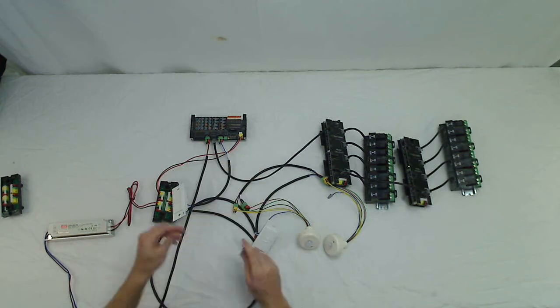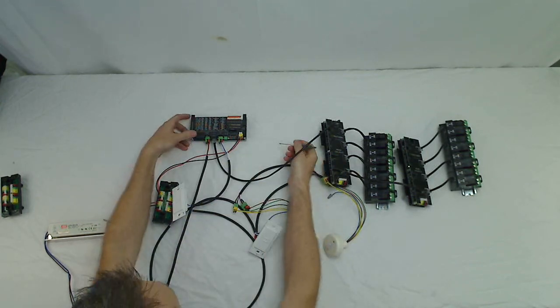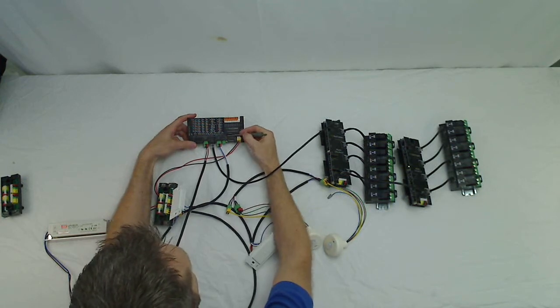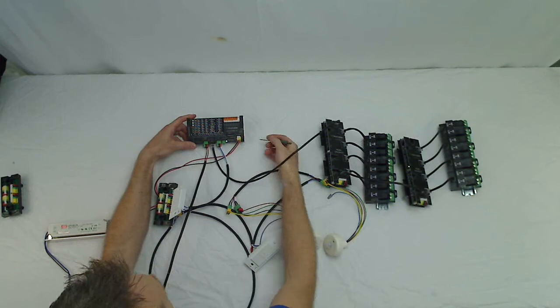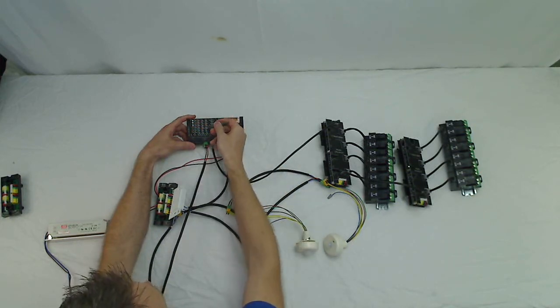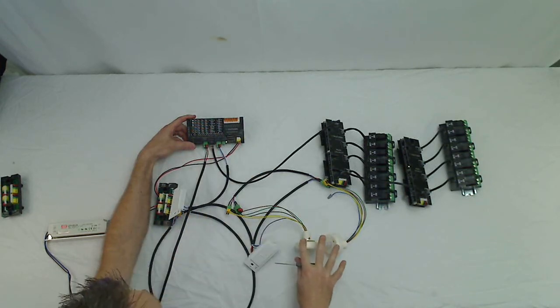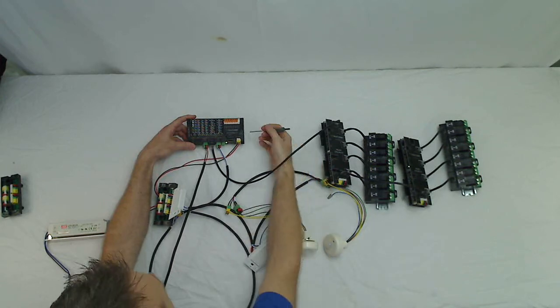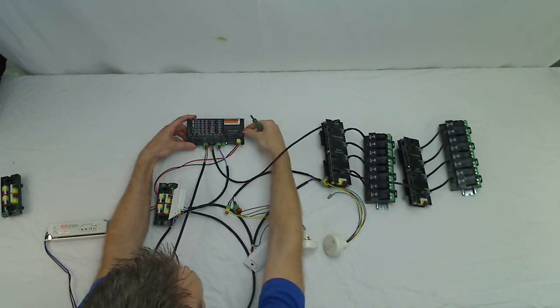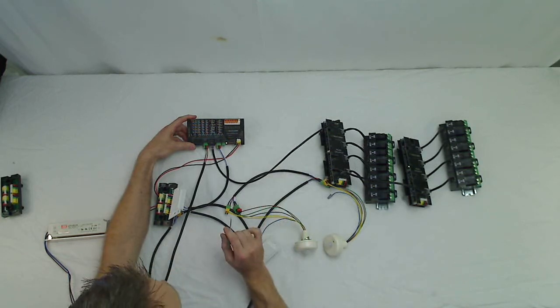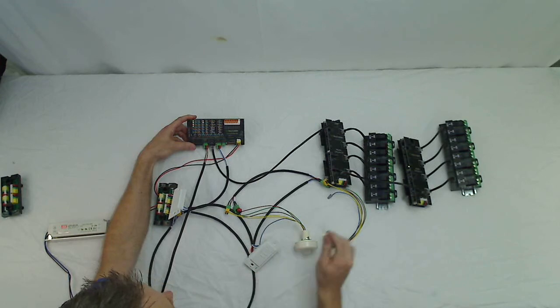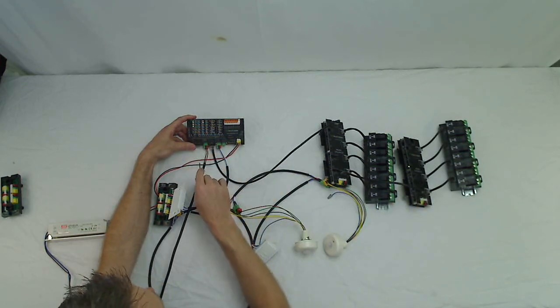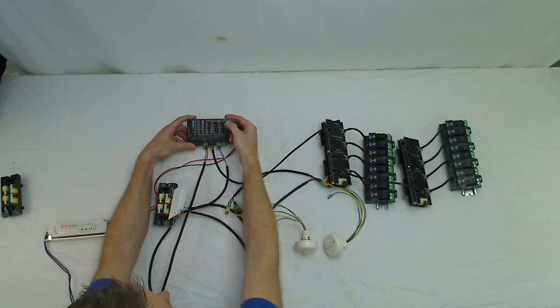So the last thing to do is everything's now wired up for the controller. We'll go to the options dip switches, and we'll turn on dip switch number seven. And we can see here, under our stations, we've already discovered station one, two, three, and four, which is our two wall stations and our two sensors. So now we're going to discover the rest of the stuff on the network. So with dip switch seven on, we press the clear discover button, and it will discover, rediscover our stations and our firing cards. So now we have our four station or input devices, and we discovered firing card number one and number two.